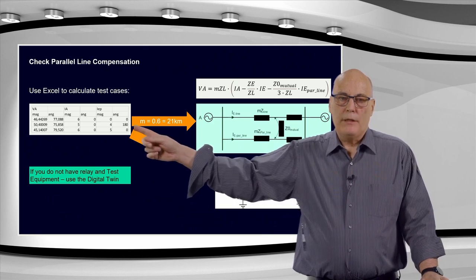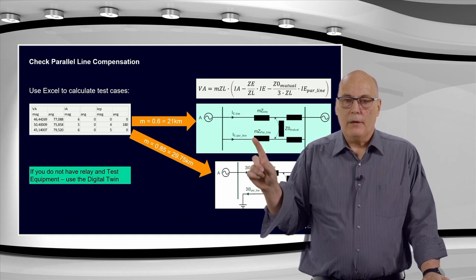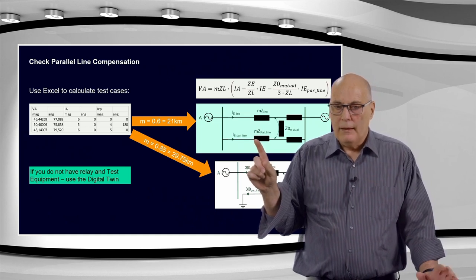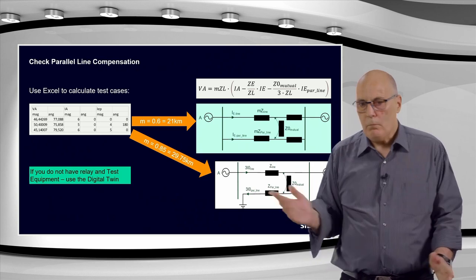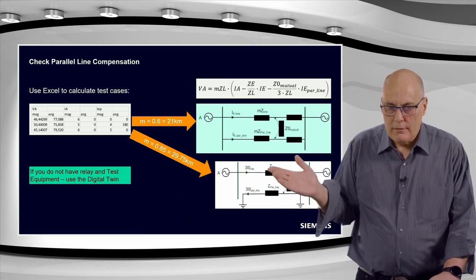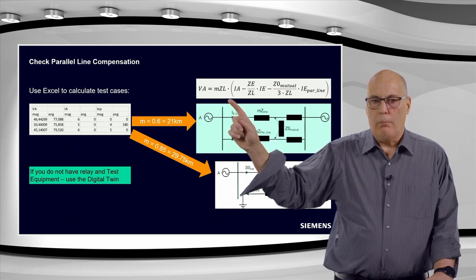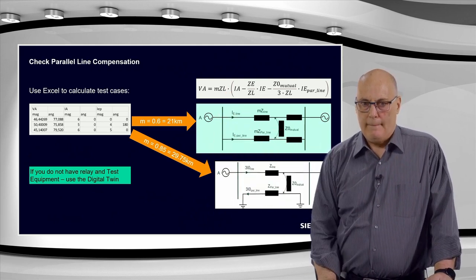So in this second test case we have 5 amps here and 4 amps over here, and the ground currents are parallel. Normal application, remote fault, and again it was at 0.6, just to compare the two results. So both of the first two faults are at 60%.